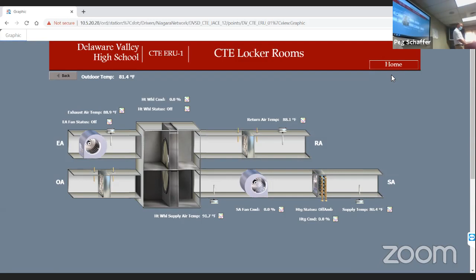I'll go back to that, Marvin, because that's a good point to make with the middle school VAV system. This rooftop unit is serving everything in color—everything gray here is a unit ventilator, and these are all VAVs. These six classrooms are actually served by one rooftop unit, so the air from all those rooms returns to the rooftop unit, mixes together, and then dumps back into the rooms. Unlike the other classrooms that are independent of each other, here you're mixing all that air together.